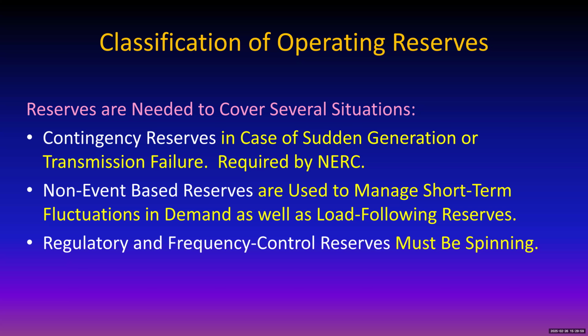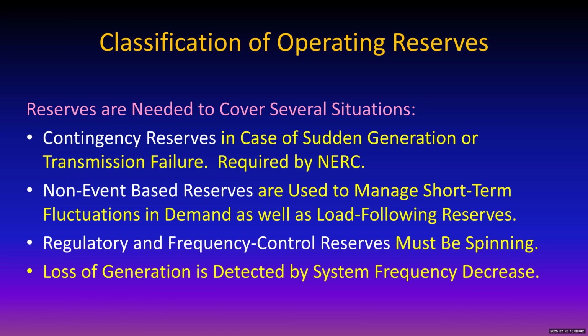Interesting stuff there. Loss of generation is detected by a system frequency decrease. That makes sense, because all of a sudden everybody else has to work harder, and when a generator has to work harder, it slows down instantly until it's able to burn a bit more fuel and get its speed back up. But during that moment, there's going to be a drop in frequency, and if the existing generation can't manage it, something else has to come on and help out.